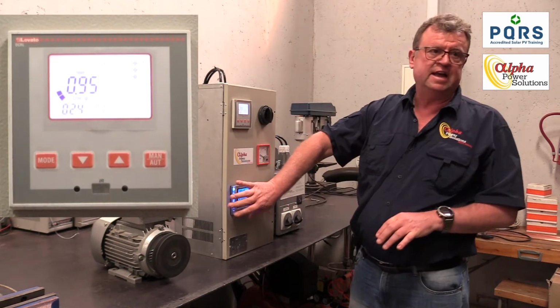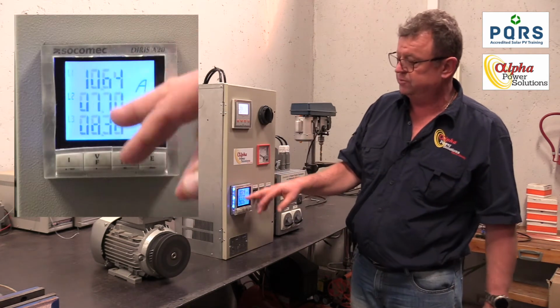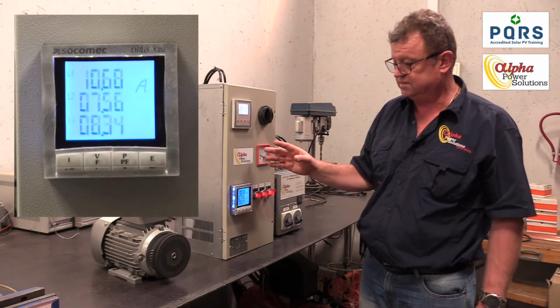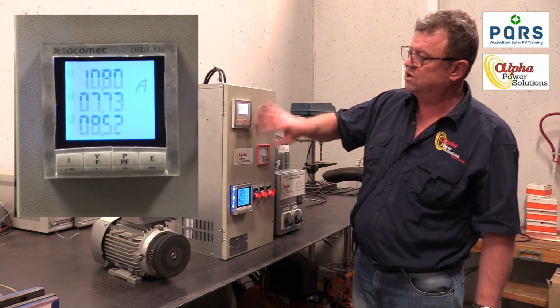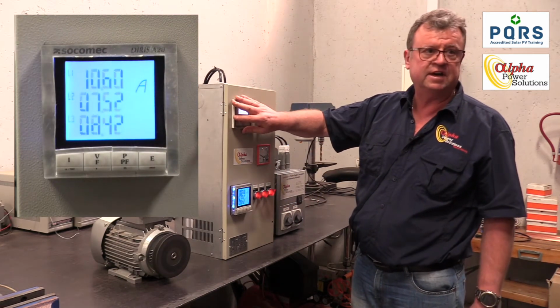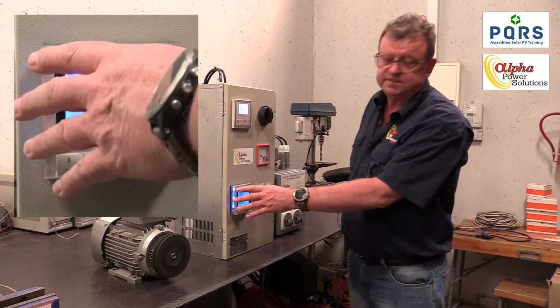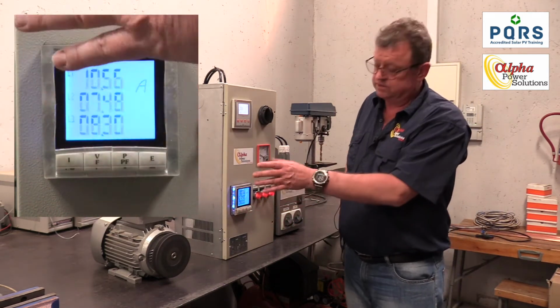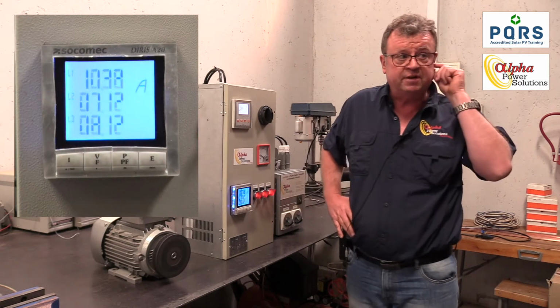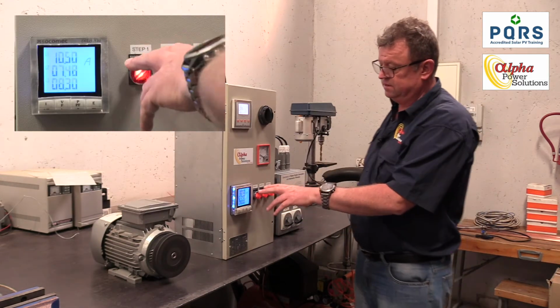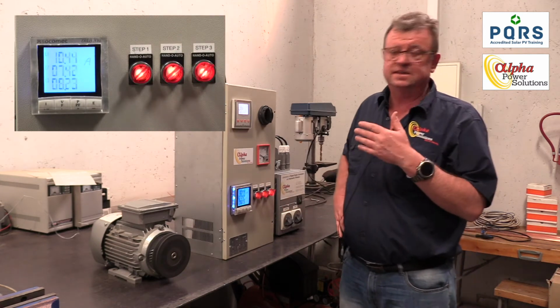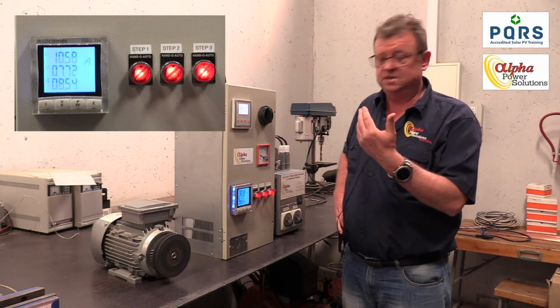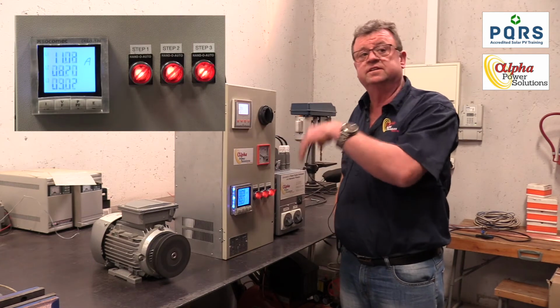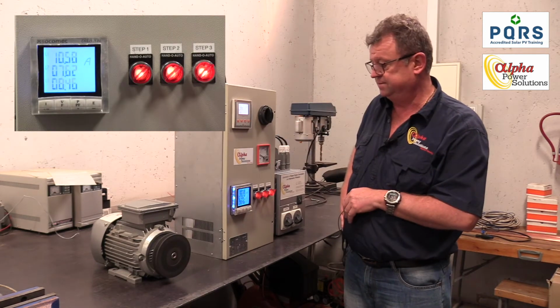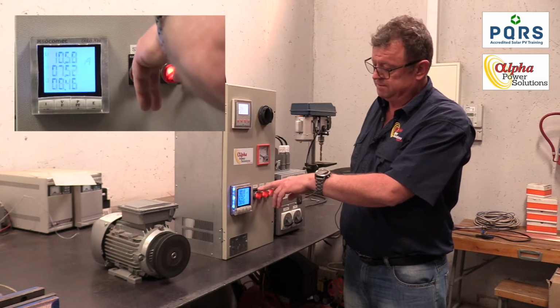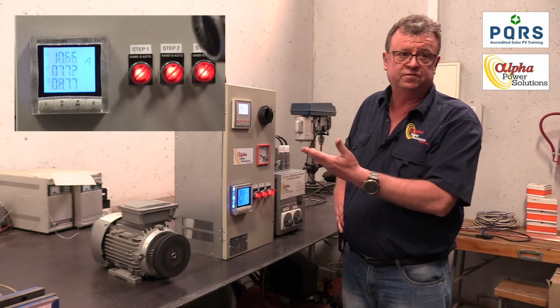This device I've only added so that you can see the current dropping on all 3 phases. So it's a 3-phase system, and because you can't see that information in this little device, I've added a separate meter just to show that the current drops dramatically when you put the power factor correction system on. These are just selector switches that can either bring in the steps or energize the contactors inside the power factor correction panel, and so you can put them in manual or in auto or off.